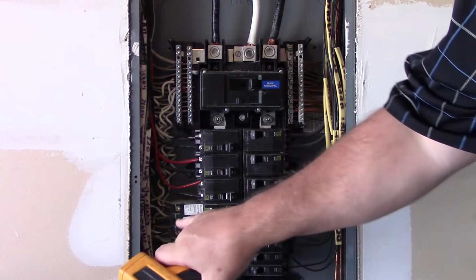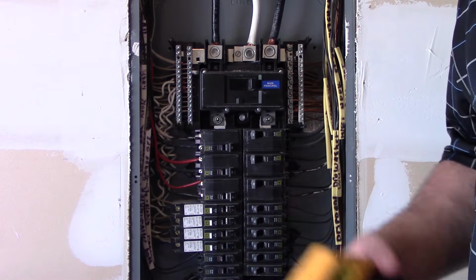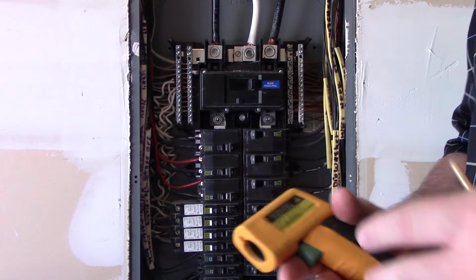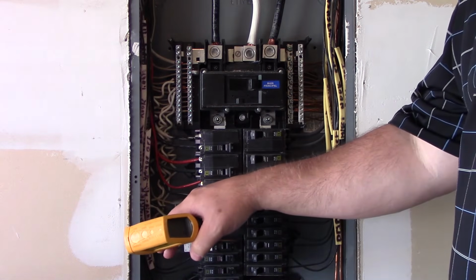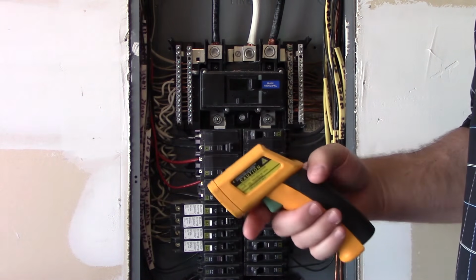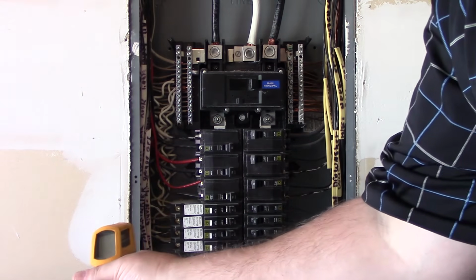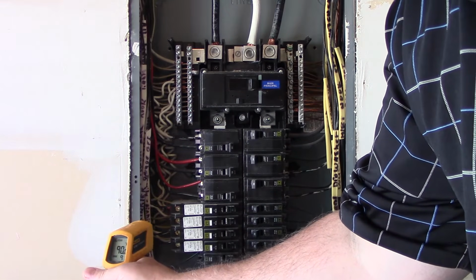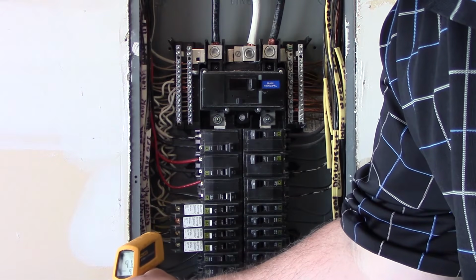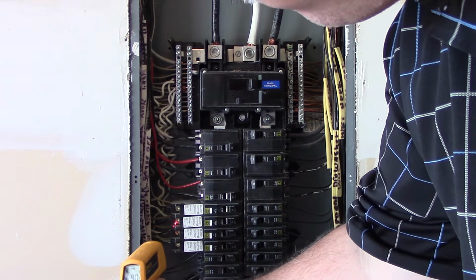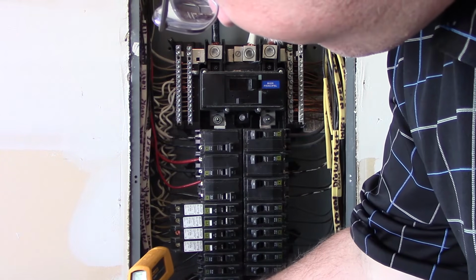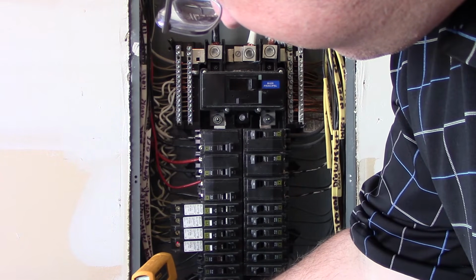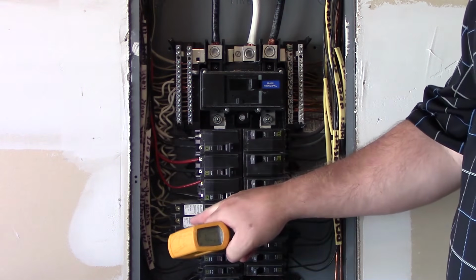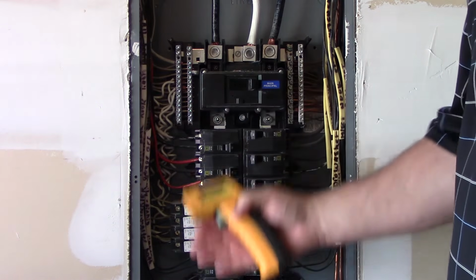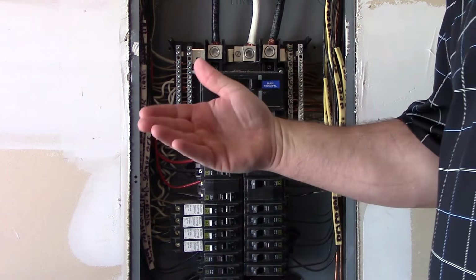One thing you will notice different is these AFCIs. The AFCIs tend to run about 10 degrees warmer. It can fluctuate a little bit. They have circuitry in here that's going on and they generate some heat, but nowhere near anything to be worried about. I'm going to shine it in here and see what I get. That's a 90, 92, 90, and about 90. Basically, these were 80 and these were 90, so it's roughly about 10 degrees.